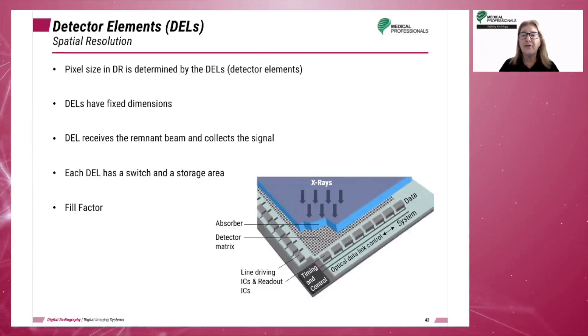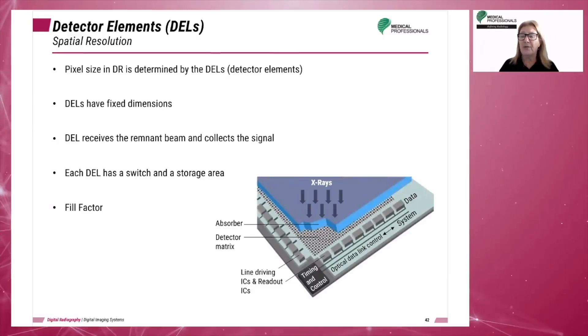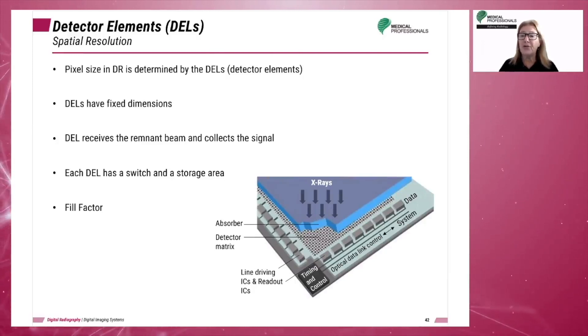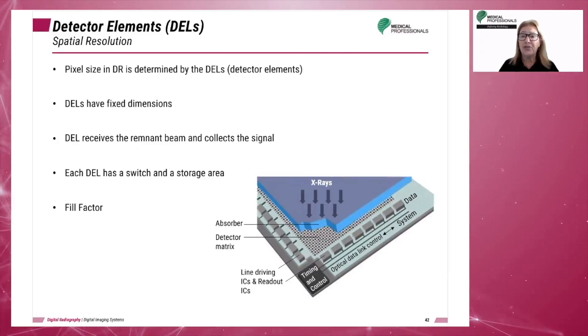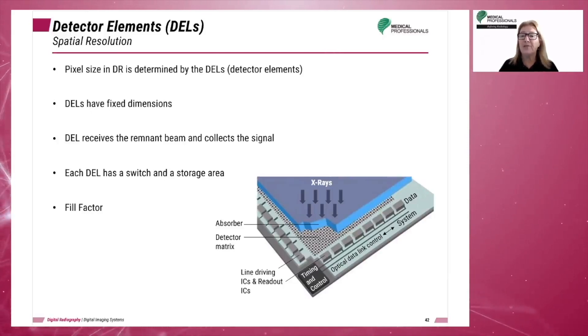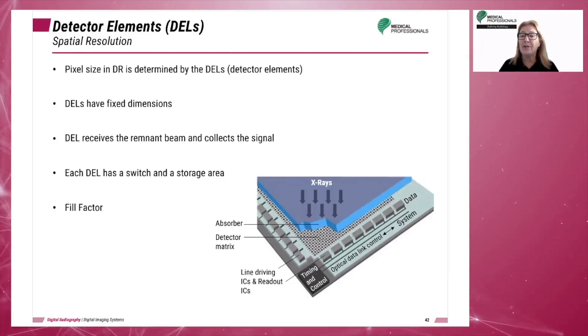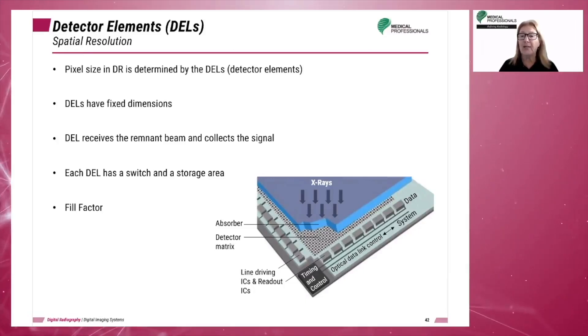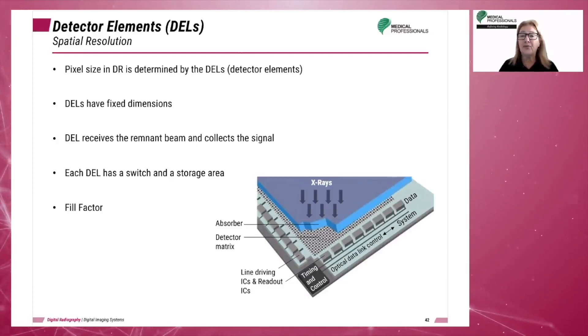Thin film transistors are elements in the panel of pixels or detector elements. Pixel size in digital radiography is determined by the size of the detector element and affects pixel pitch and spatial resolution. Detector elements are positioned in a matrix that allows the charge pattern to read out on a pixel by pixel basis. Each detector element includes a sensing area, the capacitor, and the thin film transistor.